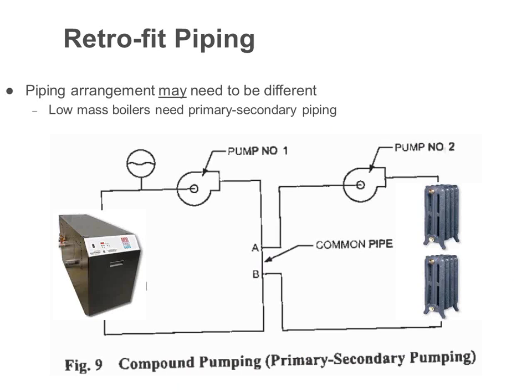All right. But basically in here, this is a typical primary, secondary, very simple application. We're showing the circulator or pump number 1, our expansion tank. There's our boiler, a high efficiency boiler. Basically all that pump is concerned about is the pressure drop of that boiler. These low mass boilers have a very high pressure drop, so they cannot deal with that second pump, the pump that was originally there to handle the whole system plus the new boiler. So basically we've got to go to a primary, secondary type piping.